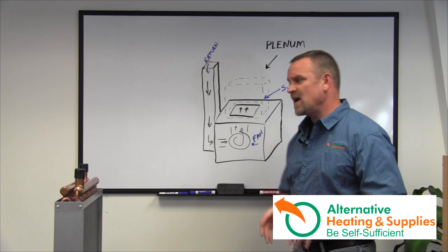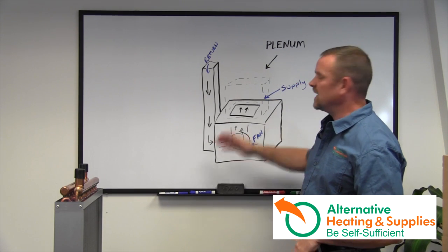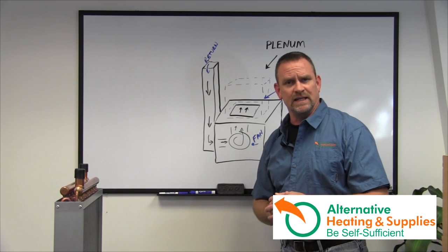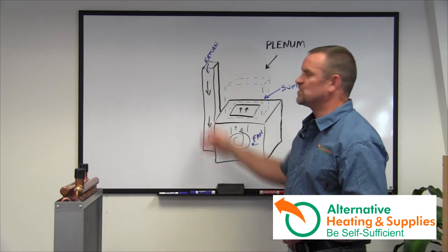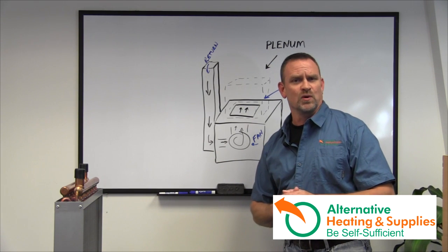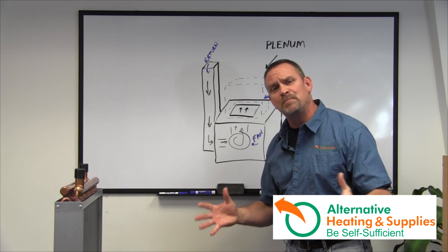Another thing that people always ask me about is, hey, instead of mounting on the supply, can I mount it on the return? Yes, you can technically. I do not like it because usually the returns are much smaller. They're usually long and thin. They're difficult to work with. But you can put them in there.